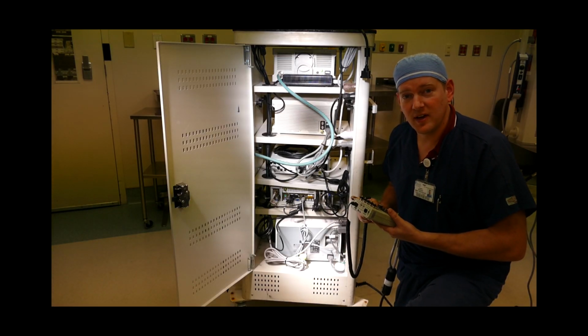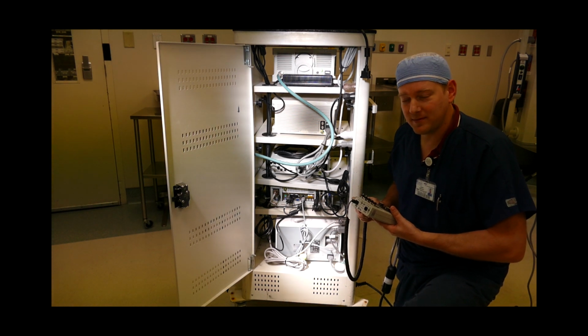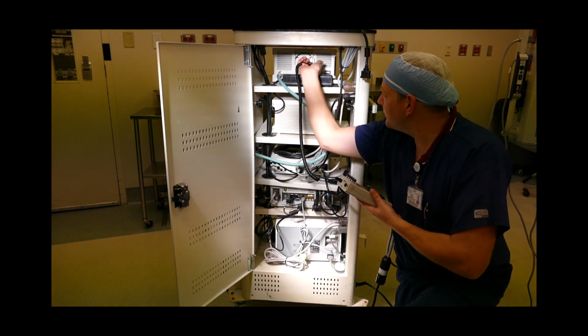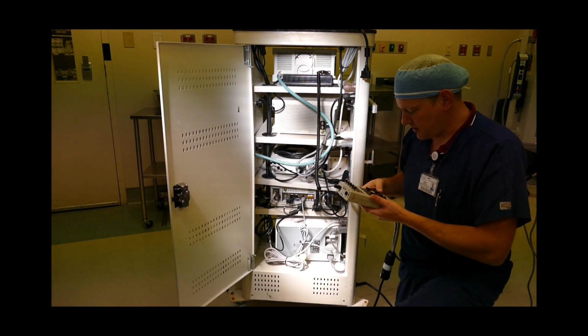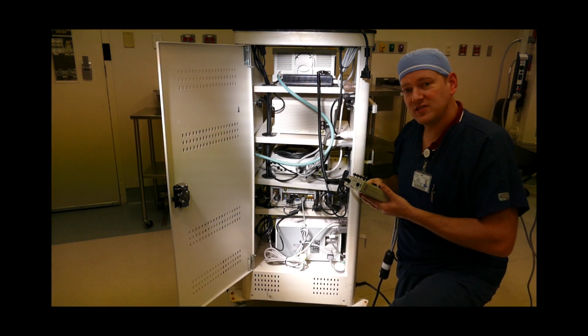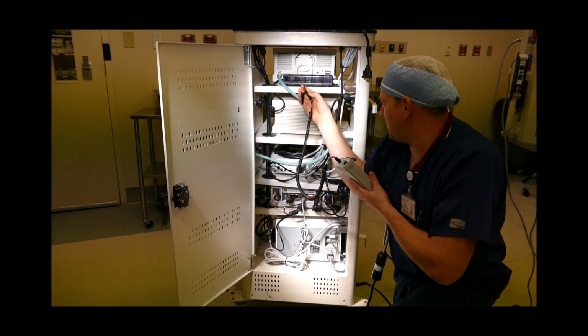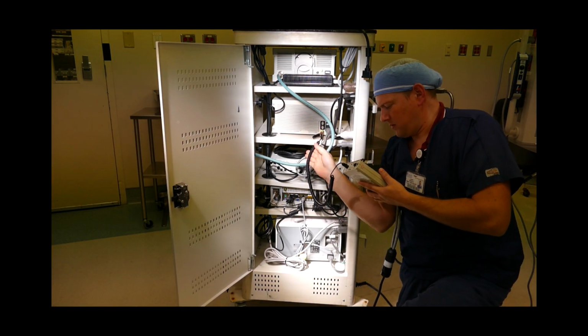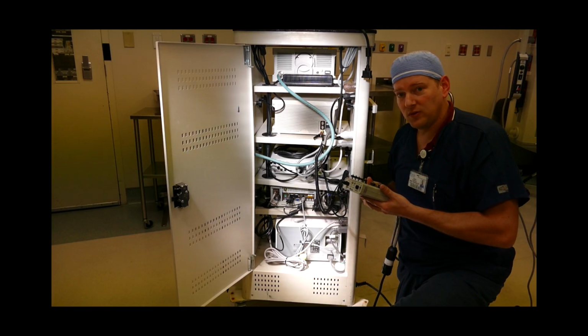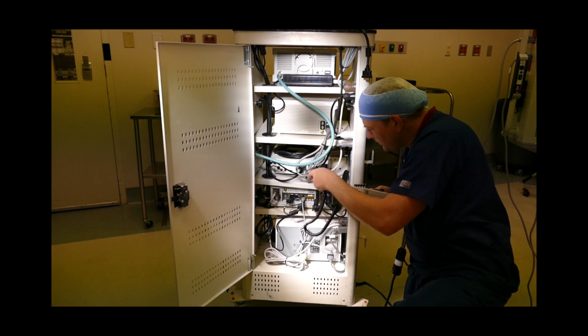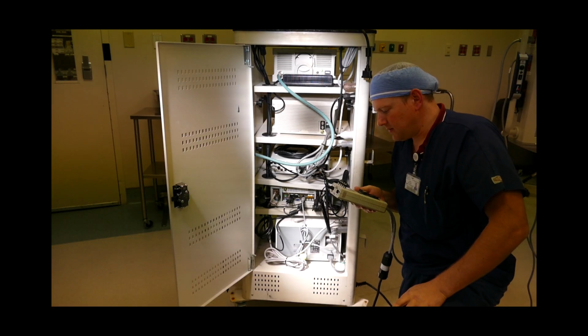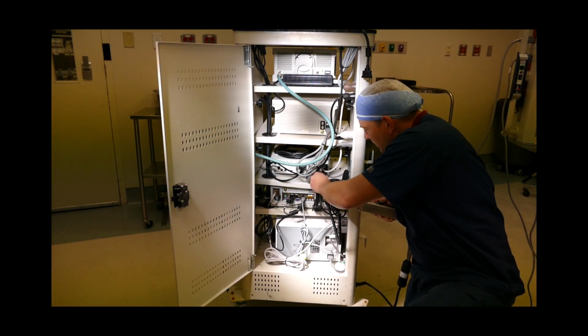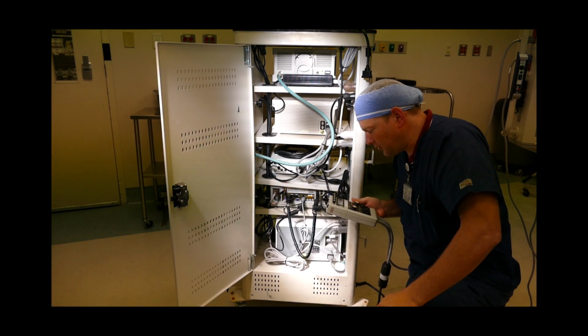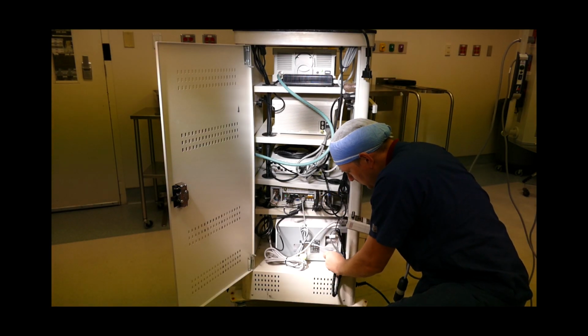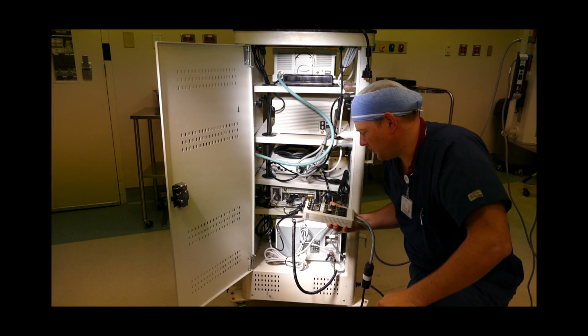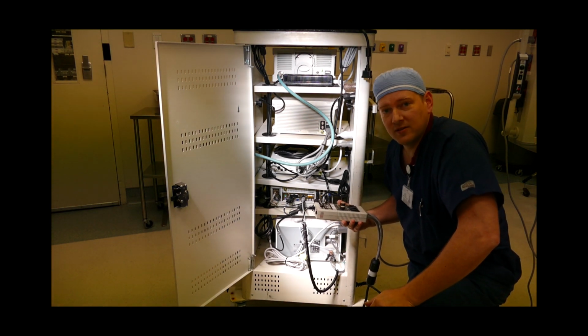Now the earth resistance test for all the components inside the cabinet. So we'll start at the top one, connect to the ground lug. Now I've got 0.17. Connect to the next one, 0.23. The next one, 0.23. 0.23. And 0.26. So all these components test out the ground.